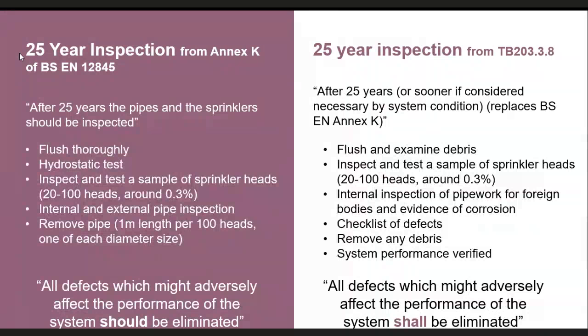Annex K calls for 1 meter length of pipe to be removed, so Annex K is insisting that you remove pipe. TB203 doesn't actually insist that you remove pipe. It just says you've got to internally inspect it. So for me, that opens the door to running cameras, taking pipe samples, or even using ultrasound scanners as an alternative method of internally inspecting the pipe. And again, we have a very similar statement in terms of what you need to do at the end, but Annex K says should, and TB203 says shall.